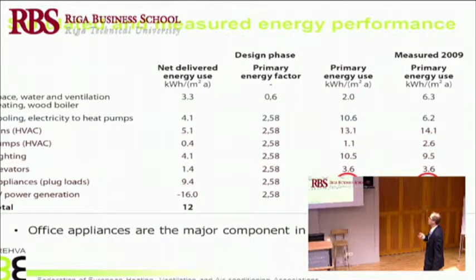Fans correspond very well to the prediction, and pumps a bit more, lighting is predicted very well, elevators very well too. But what was not well predicted are the office appliances, meaning all the computers and office equipment, because that number is extremely low and cannot easily be achieved in practice. In reality it's a factor of 2 or even higher. Still, this number is very, very low, showing a genuinely good performance in that building.